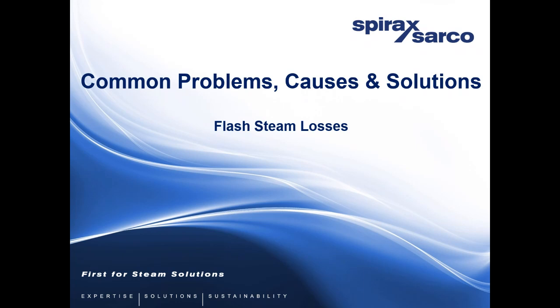With mechanical steam traps, going back to the previous question of the traps only lasting a year, we would expect to see in a healthy system those traps last 2 to 3 years depending on use. So when it comes to inspection and service routines, inspection should be every 6 to 12 months. Service should be every 2 to 3 years. So I think that's probably right. Again, those times can be dramatically shortened by an unhealthy steam system. I don't know if there's anything you'd like to add there, Anthony. No, I think that's well put.